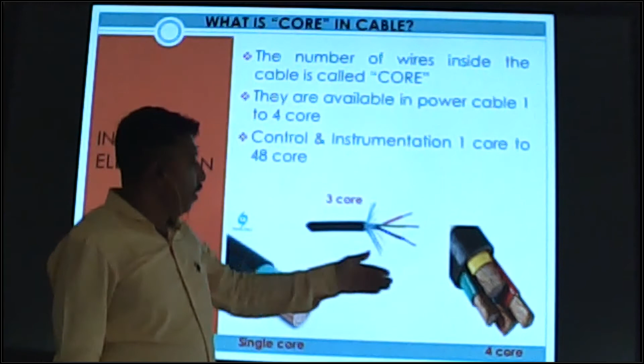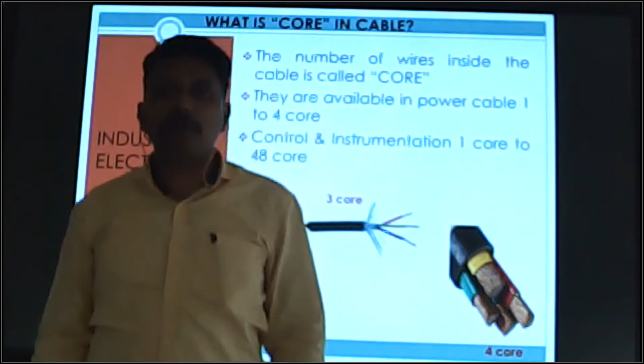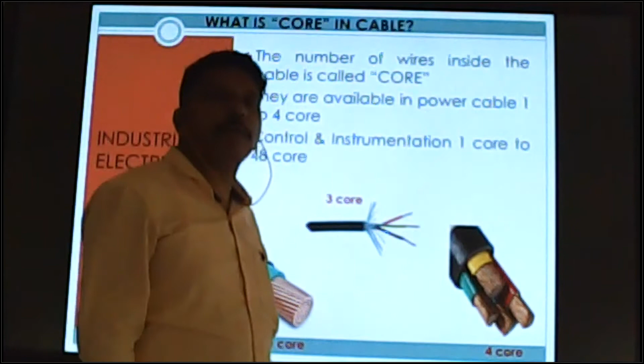4 core, there is the 4 core already. This is red, yellow, blue, and earthing. Especially this type of cable is used in 3-phase motors in industries or buildings, where there is no need to use neutral. One is used for earthing, and the other 3 are used for the phase purpose.